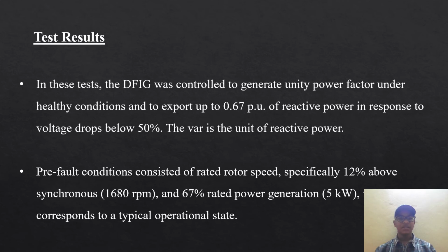Test results. In this test, the DFIG was controlled to generate at unity power factor in healthy conditions, and to export up to 0.67 pu of reactive power in response to a voltage drop below 50%. The VAR is a unit of reactive power. Pre-fault conditions consisted of rated rotor speed, specifically 12% above the synchronous 1680 rpm, and 67% rated power generation, 5 kilowatt, corresponding to a typical operational charge state.